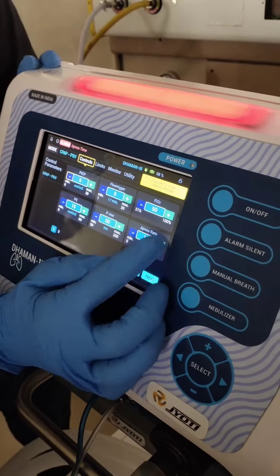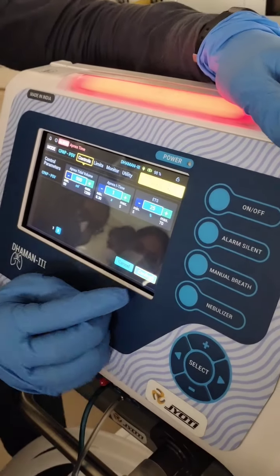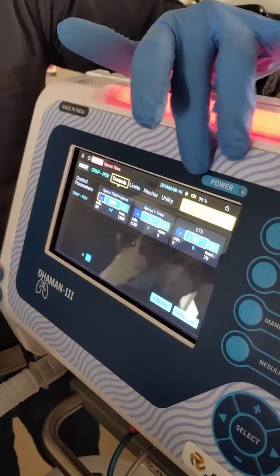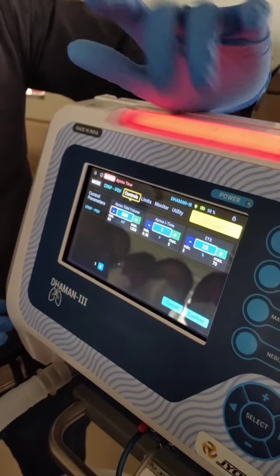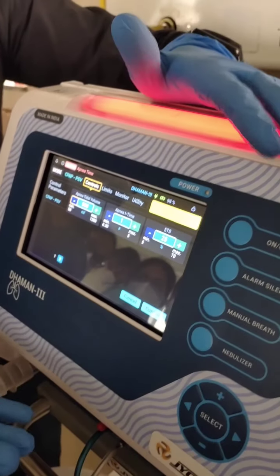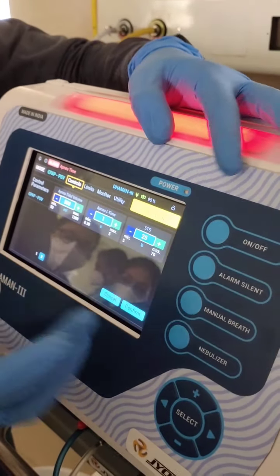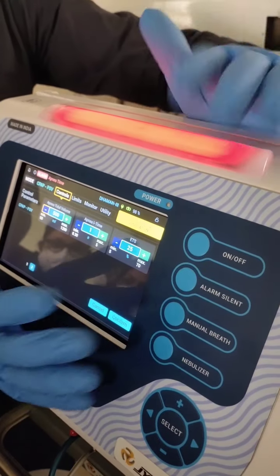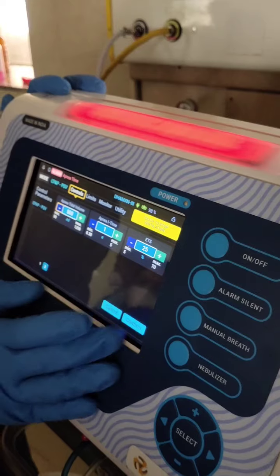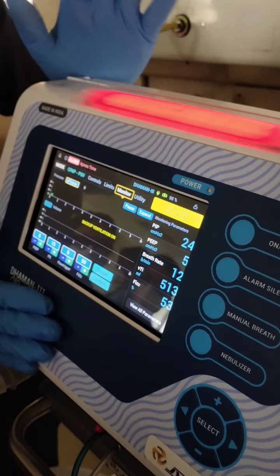And then apnea time, we know all that, the breath rate. And then next we have apnea tidal volume, apnea inspiration time and ETS. So ETS is the expiration trigger sensitivity. You don't have to change it. If you are facing any difficulty, you have to ask BME for help before that, then only you have to change it. Otherwise, this is the default value. Don't change it. Other things are all the same only.